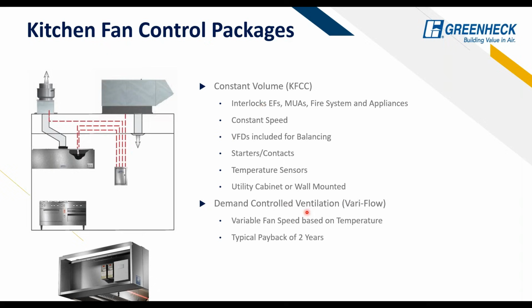With demand control ventilation, the temperature sensor inside the hood is going to look at the temperature sensor in the space. And as the temperature sensor in the hood starts to rise every 5 or 10 degrees, that is an adjustable value. Every 5 or 10 degrees or so, it'll start to ramp up more and more on the exhaust fan all the way up until it gets to that max point.